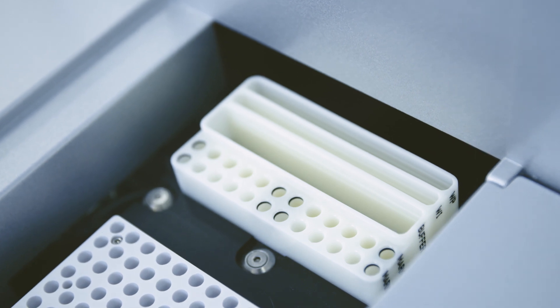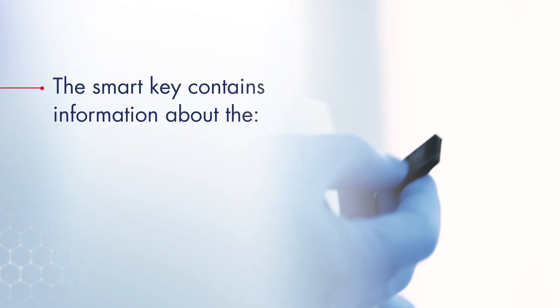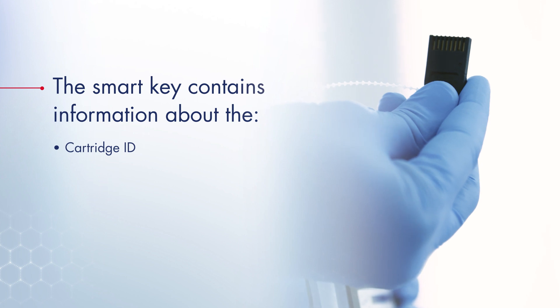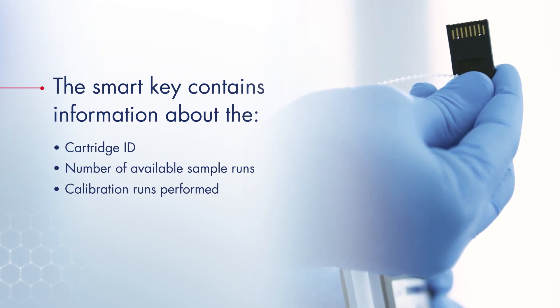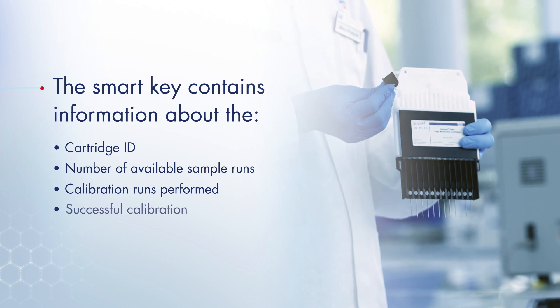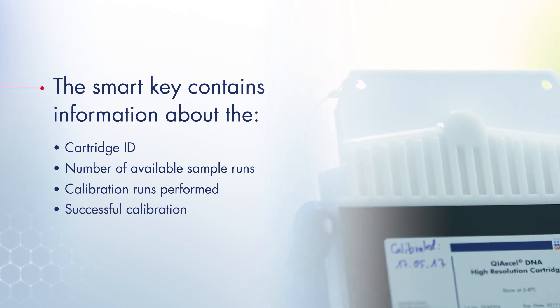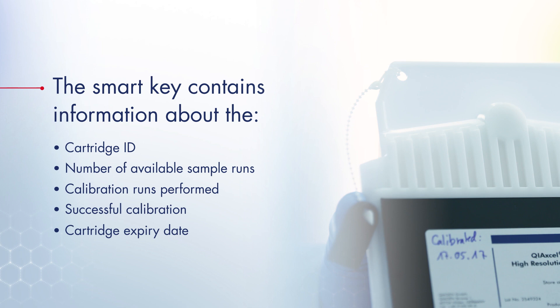Load your samples, markers, and buffers. The smart key contains information about the cartridge ID, number of available sample runs, calibration runs performed, successful calibration with the QIAxcel Advanced, and cartridge expiry date.